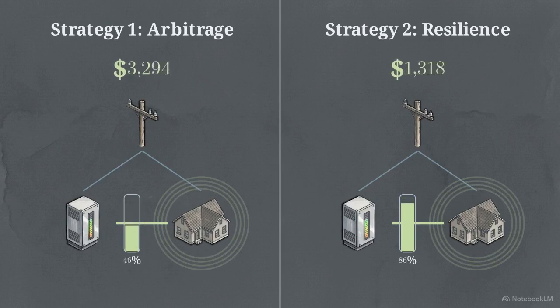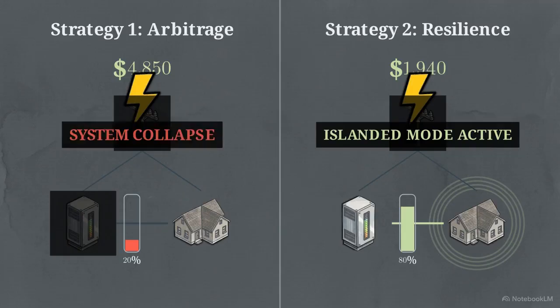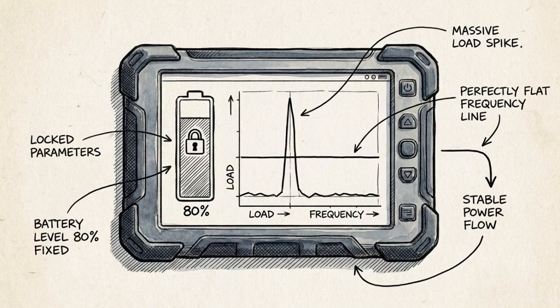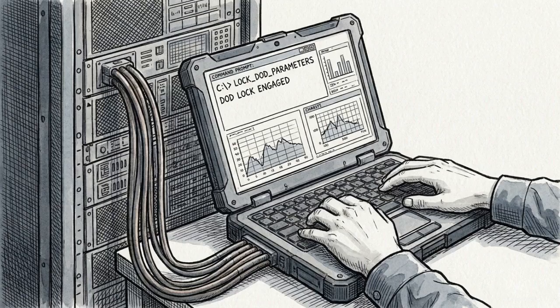Strategy 1 uses the battery aggressively for energy arbitrage, discharging it heavily during the day to offset peak pricing. If a major fault isolates the grid while the battery is at 20%, the system lacks the kinetic reserves to survive a load spike and collapses. Strategy 2 prioritizes the microgrid as an emergency reserve, holding 80% capacity while capping cost savings. By strictly holding 80% of its capacity, the system can confidently regulate frequency and absorb heavy load spikes during total isolation. Maximizing resilience requires a conscious, daily sacrifice of the battery's economic value.